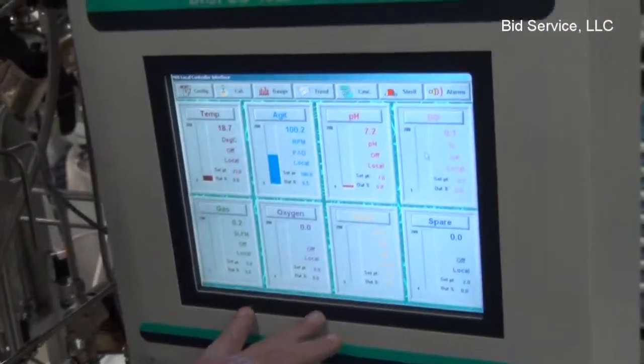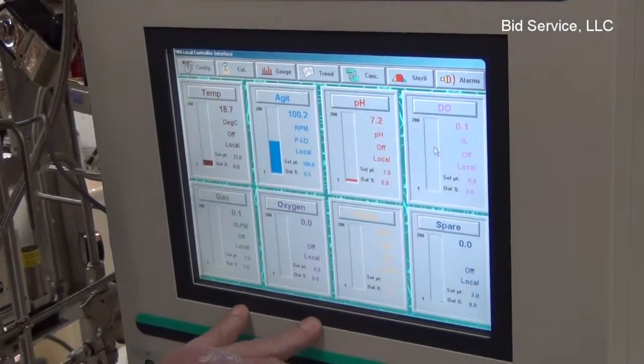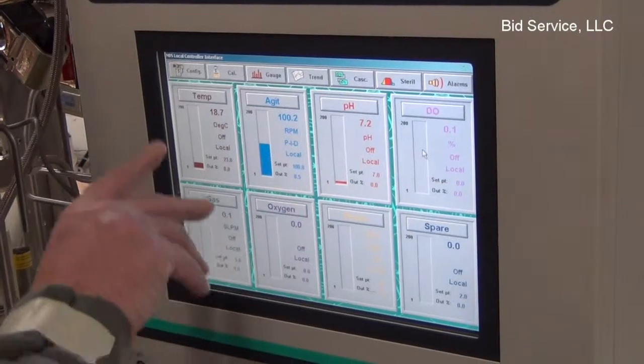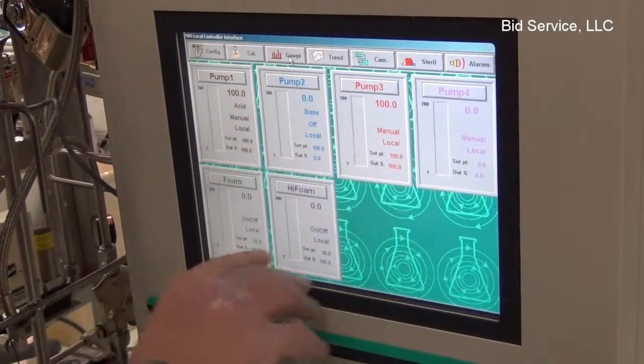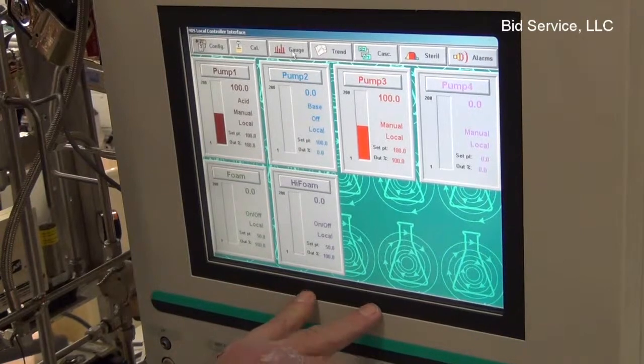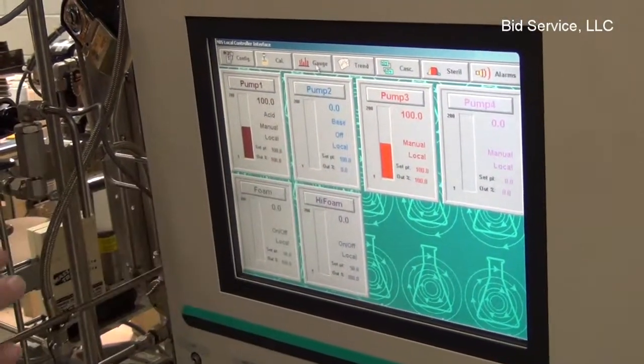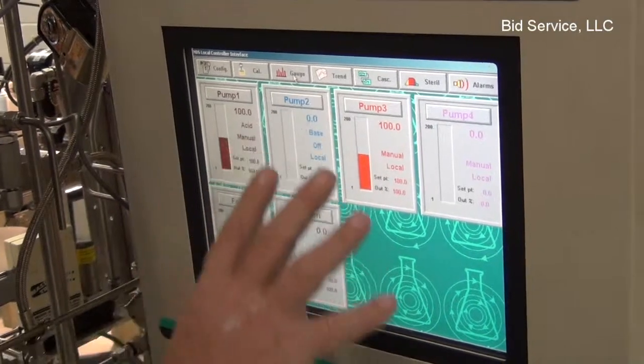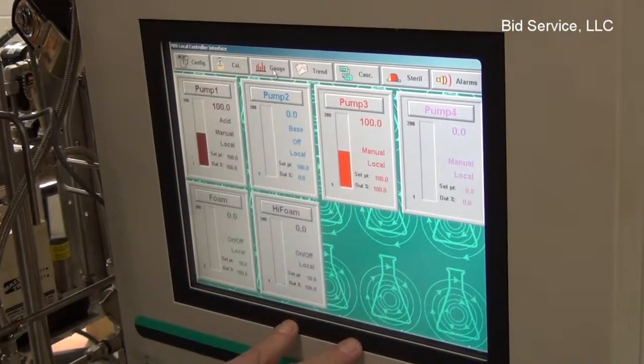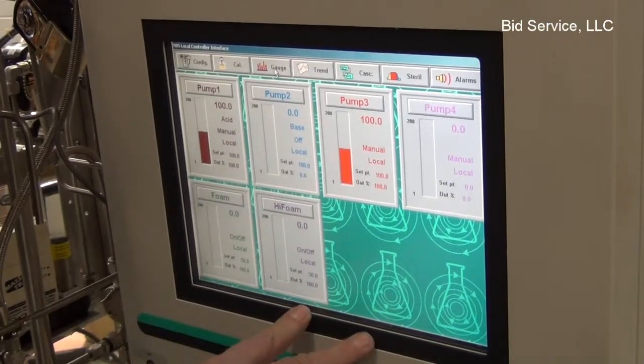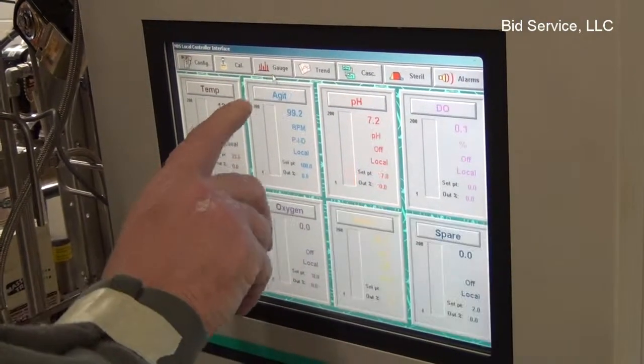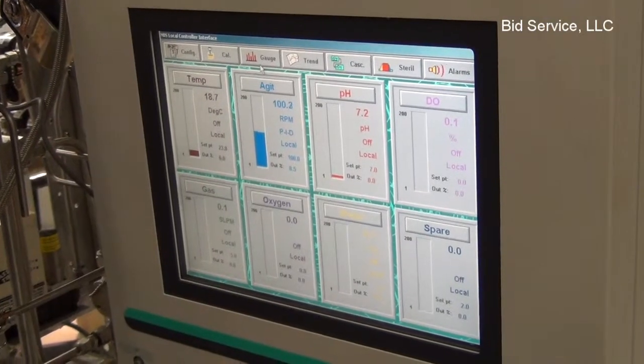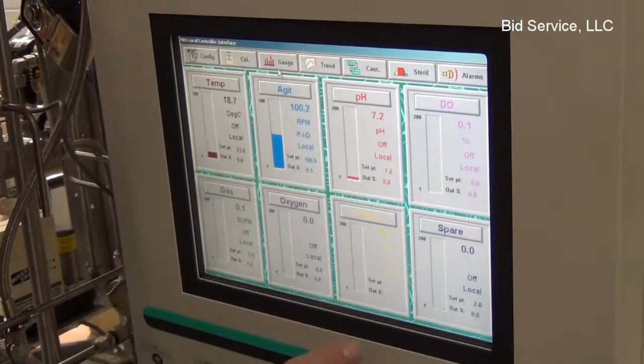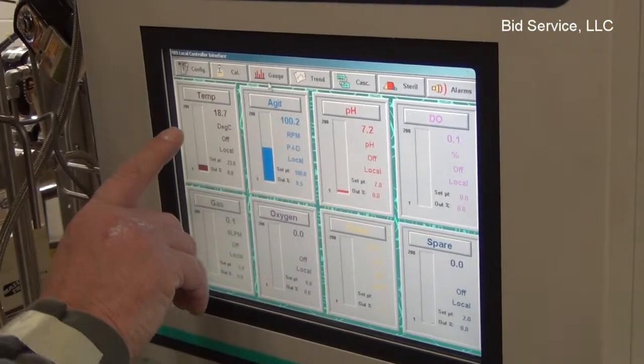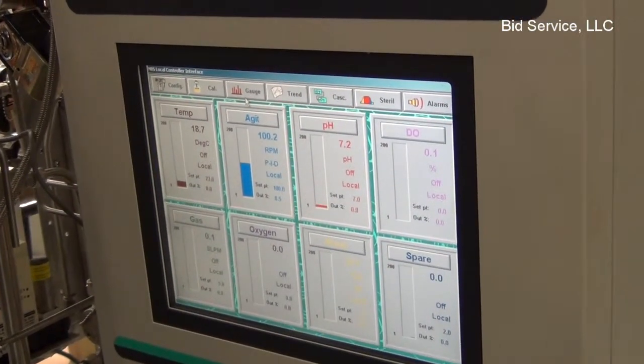On our screen here, we are at the gauge screen. This screen appears as the first screen after you do a normal power on. Go to the gauges again, and it shows you all the different possible loops. Many of these are not actually on the system, so you cannot use them, but I wanted to leave them there so that in the future, if you wanted to add them, you could with less difficulty than trying to add them from scratch. In the meantime, some of these, like for instance the pH and the dissolved oxygen, are not functional, and they have been turned off in the configuration.